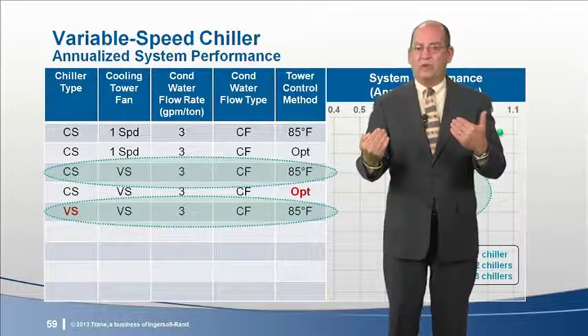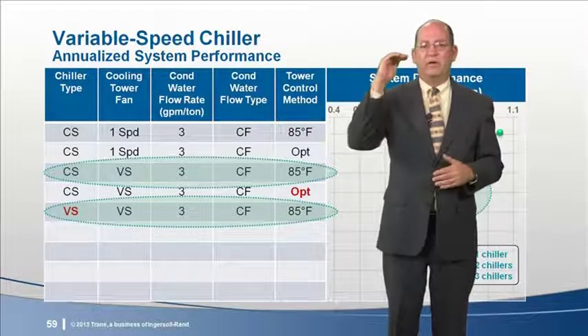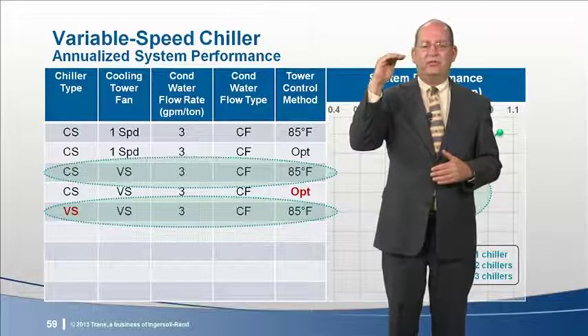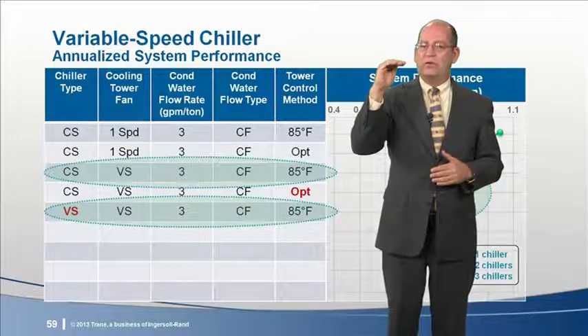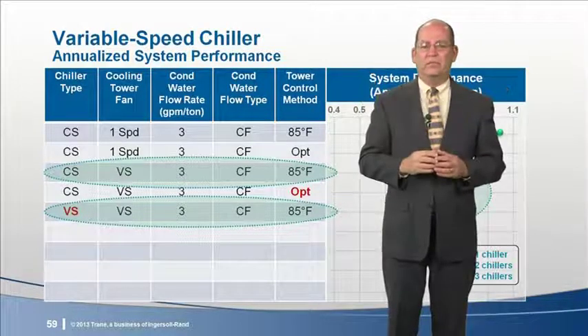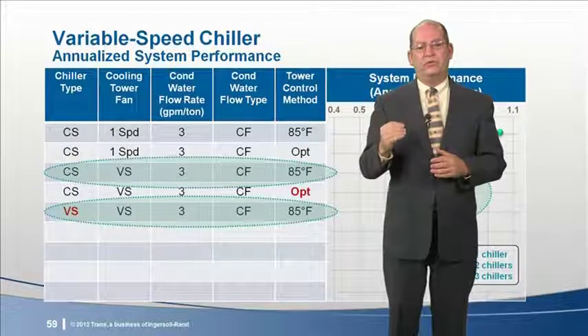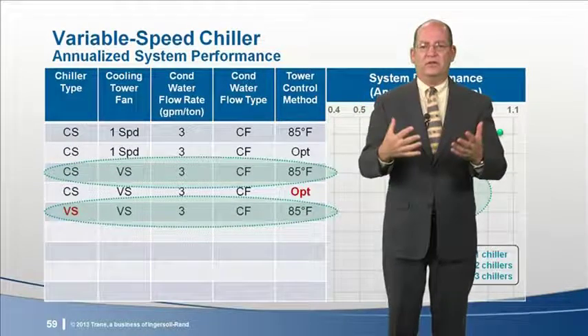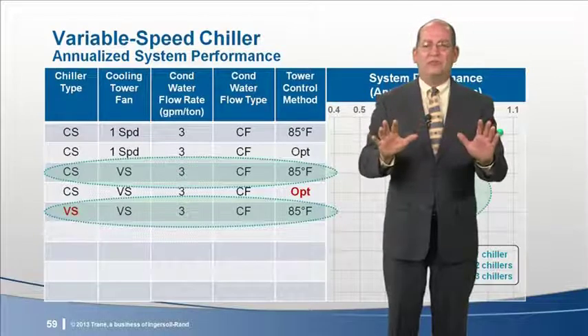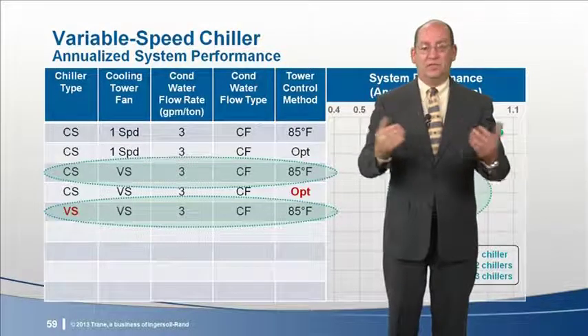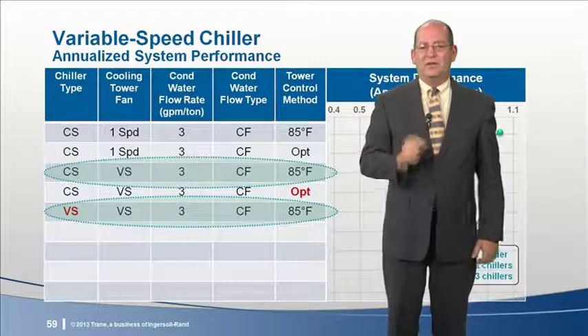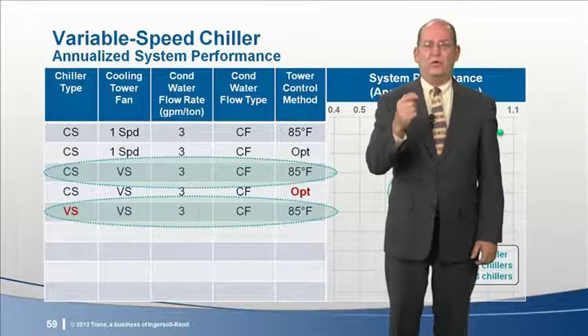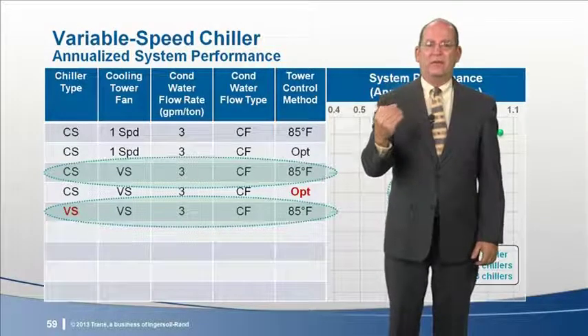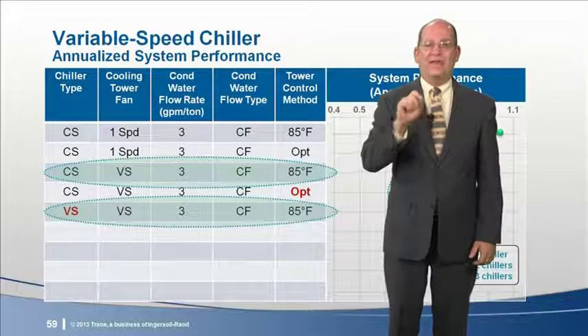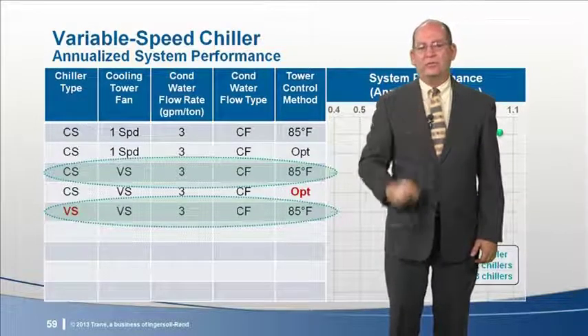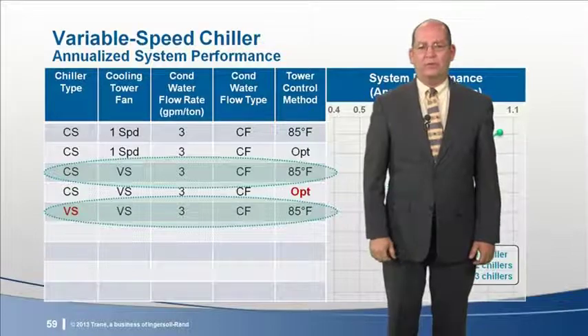Assuming a constant chilled water set point and a tower control to maintain its design temperature, the leaving condenser water temperature only changes a little. And that change is proportional to the load and the design delta T. This change is not enough to offset the inefficiency of the variable speed drive. This shows us that it's imperative to apply chiller variable speed technology appropriately and that proper system design and control are critical.